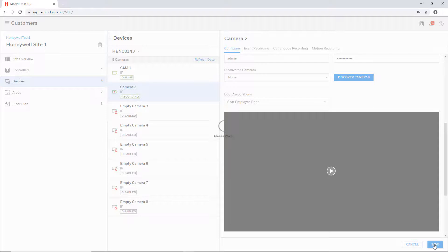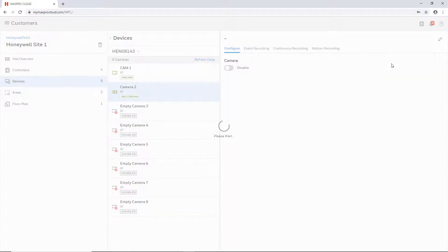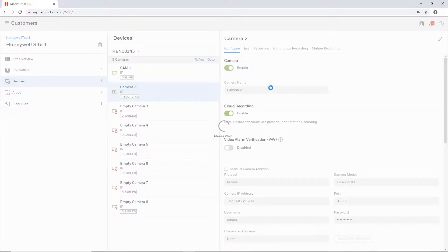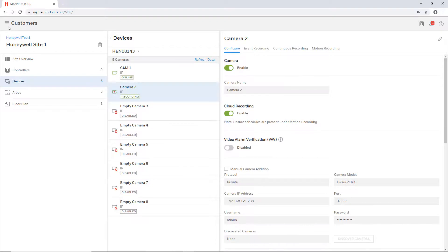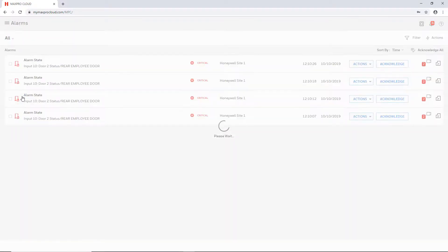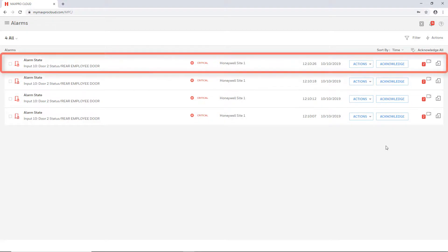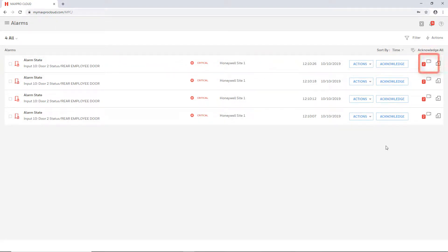Once the association has been created, anytime an alarm or event happens on that specific door there will be an option to pull up a live view of the associated camera from the alarms page. Select the menu icon in the upper left and click on alarms. If there is an alarm or event for the associated door it will be listed here. There will be a camera icon on the far right if associated with a camera. Click on this icon to pull up a window that immediately loads the live view for that camera.